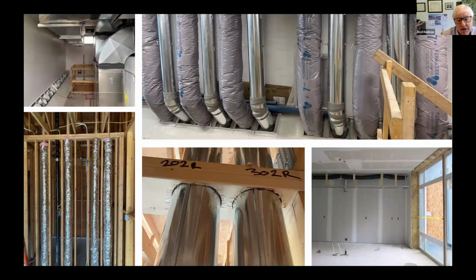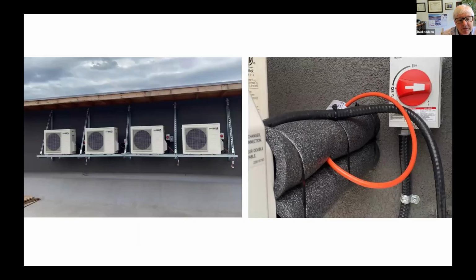Central ducts, we take everything down to 5-inch ducts by the time we go to the units, because then we don't need fire and smoke dampers where we penetrate all our fire separations. So as long as you're a 5-inch metal duct, you don't need to put all the fire dampers in. And then up in our mechanical room is where we have all the fire dampers, where it leaves the mechanical room, and the balancing dampers.